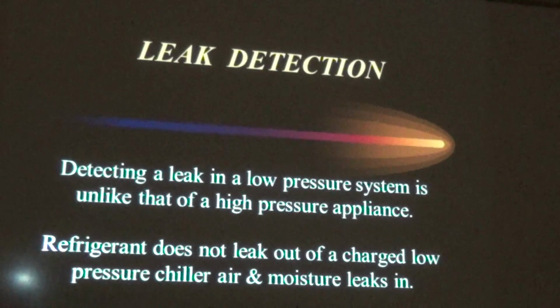So now, leak detection. Detecting a leak in a low pressure system is unlike that of a high pressure appliance. Refrigerant does not leak out of a charged low pressure chiller. Air and moisture leaks in. So the way that we check this is that if you have accessible, there's going to be a discharge tank with the purge. Most of these are automatic purge units, so it's doing it for you. So when you see the tank of the gunk that's being discharged get to be too much, it tells you something. It tells you you've got a leak.